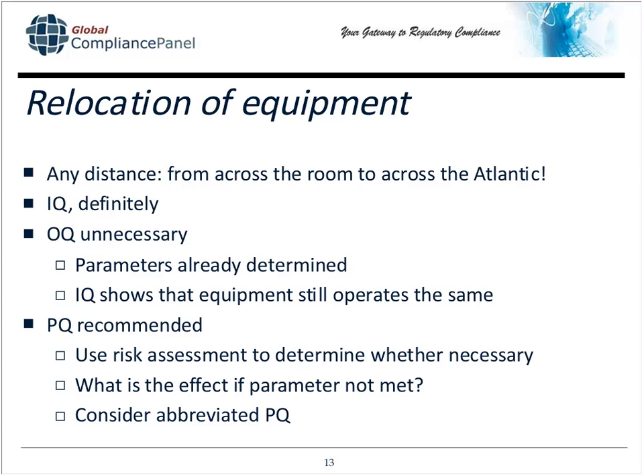So what's the effect if the parameters are not met? Let's use the sealing and packaging machines. I'm not going to do a PQ, or I don't want to do one because I want to get this piece of equipment back to service as quickly as possible. What's the effect if my parameters are not met? So I might have discolored seals, but they're complete seals. So that's just a cosmetic thing that my end users might say these don't look good. Well, unfortunately, now let's look at the other end of my parameter. My parameter is that the seals are complete. If something goes wrong here, and my pouches are not sealed, but my product is labeled sterile, that's a huge issue. So when it comes to a sealing machine or packaging machine, I would determine that based on the risk that we do perform a PQ.